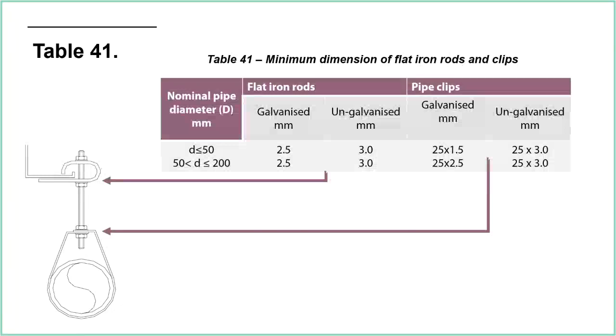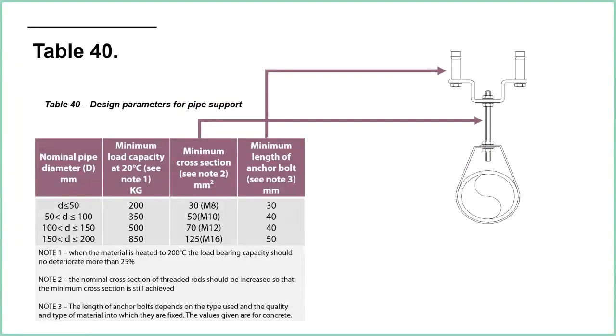Then we have table 41 and table 40. These are talking about different types of supports. So you can see on the left-hand side there we have a bracket which is gripping onto something, normally a supporting beam. And then we have some information in terms of the pipe clips and the rod sizes to be used. Similarly for table 40, we've got a different type of bracket there, and now we have different minimum load capacity, telling you the size of the bolts to use, and even the anchor bolts that are used to secure it in place. So again, all that information is there.